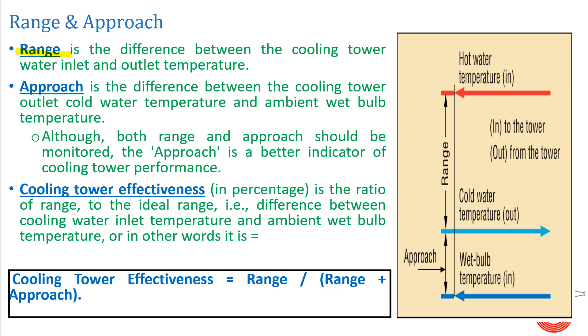Next, the terms range, approach, and cooling tower effectiveness are associated with cooling tower efficiency, and they define how to design a cooling tower. Range is the difference between your inlet and outlet water temperature. For example, if the inlet water temperature is 45°C and the outlet temperature is 34°C, then 45 minus 34 equals 11°C — so 11°C is your range.